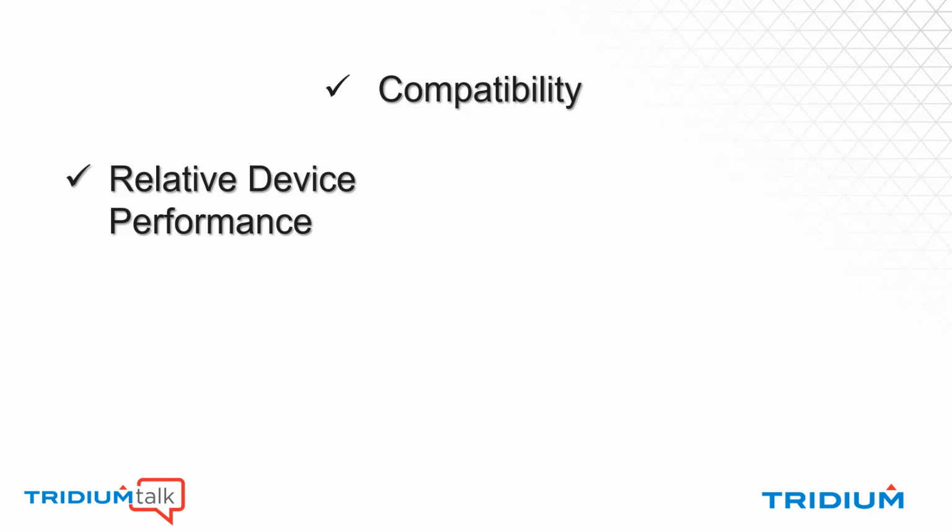But I think a much more common situation than that will be that your user is using a more recent phone or a desktop computer, a very capable device. And if they're accessing a station that's running on a JACE or Edge 10, then in this case, the JACE would have had to work harder to do the work of rendering the PX page. And by having the user's more powerful device do the rendering work instead, then you're going to see a very significant performance increase. So we think performance will be much better in most cases, but you'll just need to have a general awareness of the relative power of your user's device versus the device that's running the station.